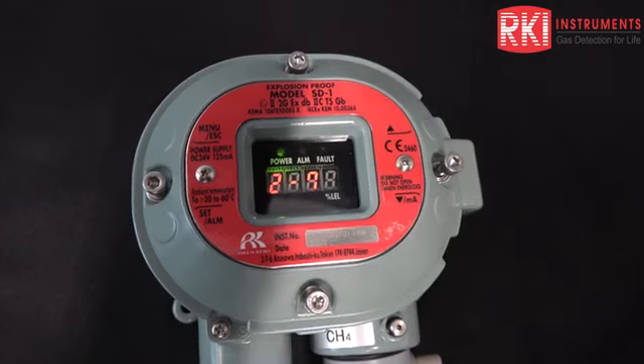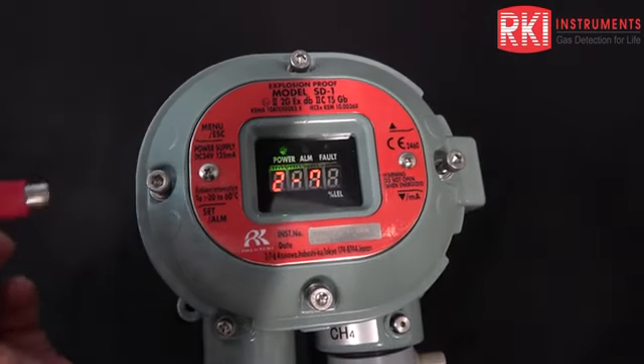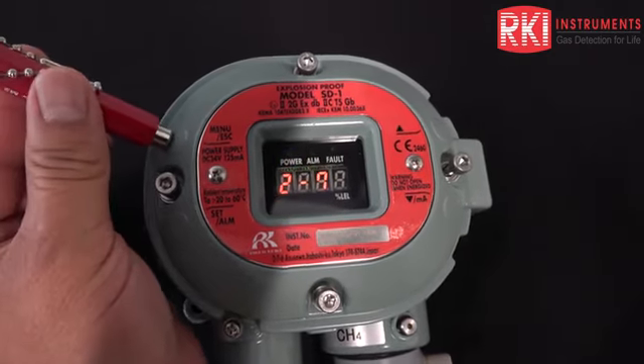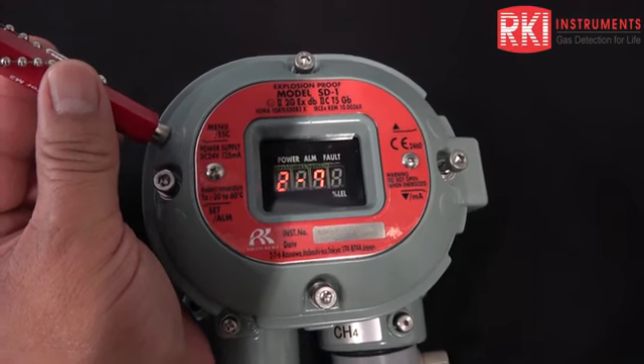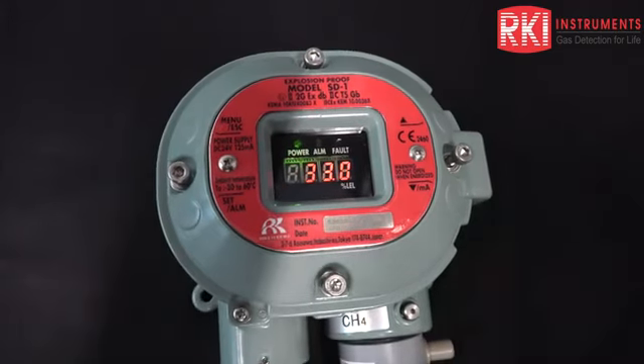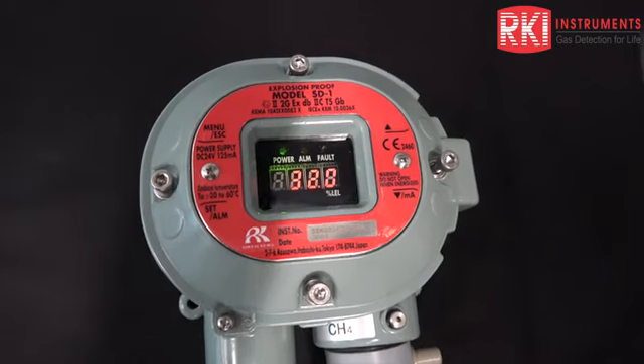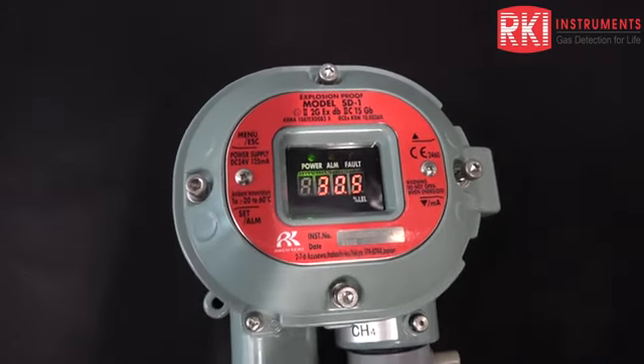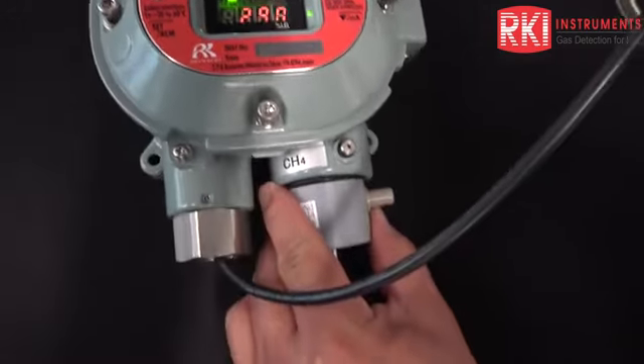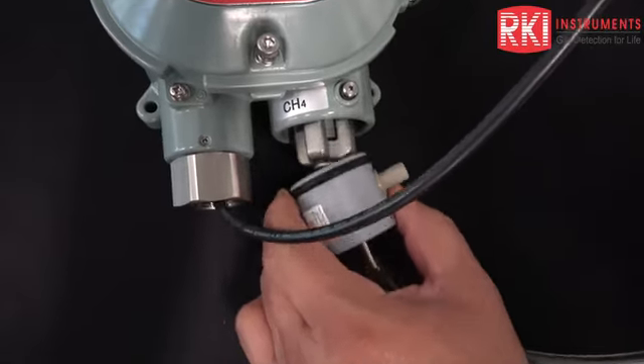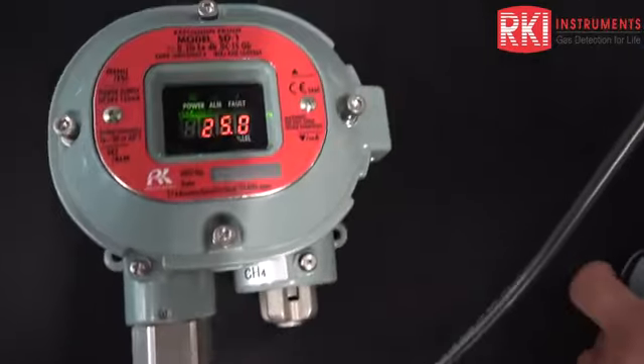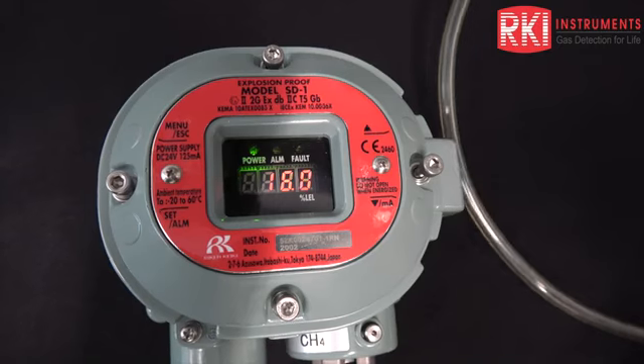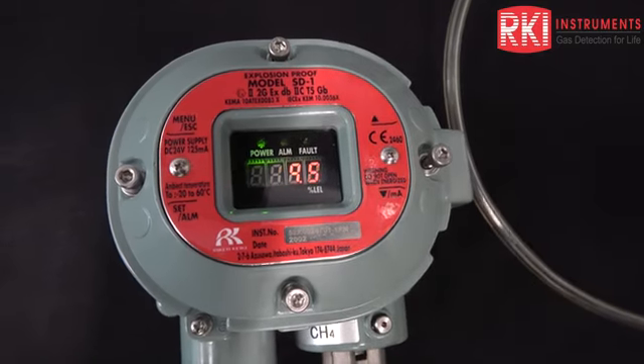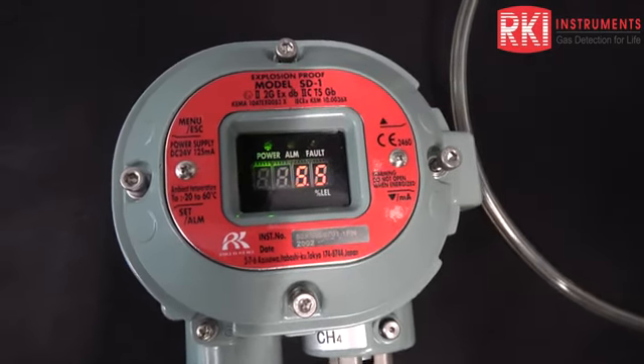Okay, so once I'm at 2-7, then I just hold down the top pad over here on the left, which is the mode pad. Just hold the key there, and it's back down to the normal operation mode. So you can see the gas is coming back down slowly, the reading I should say. And if I pull the cal cup off, then we're obviously going to decrease a lot faster. And now the reading is dropping rapidly back down towards 0.